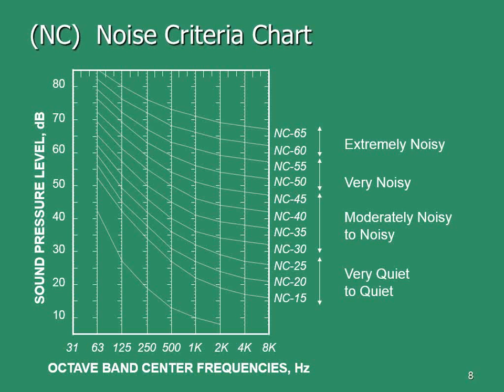All you're doing is you're not changing the noise levels you're achieving or designing to, you're just having more buildings fail spec. I've done a lot of work on military bases where, especially the Air Force, for some reason, they have this blanket spec that says all rooms shall be NC 30 or less. That's not really practical in a hangar that's 800,000 square feet where you're working on a couple of B-52s side by side. You can't ventilate a room like that and have it be that quiet.